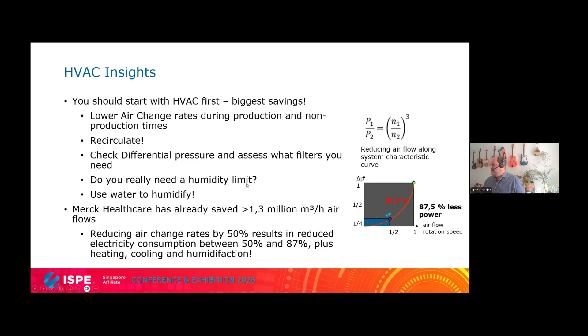From the quality perspective in an HVAC system, the clean room spec is the driver. It is not something else. It is not an aseptic guide or whatever compliance document. I've looked up all worldwide compliance documents. Mexico is quite interesting here, but all in all these documents give recommendations, not a hard must requirement. It is a recommendation everywhere, and we can even meet grade D, non-sterile, with 6, maybe in new sites even with 5 air changes per hour. It's possible and it works. There are also systems that vary the air change based on the particle load in the room, which already exist. So you could even go lower, or also during night shifts or when there's no production on nights, as I said, go even lower and so on.